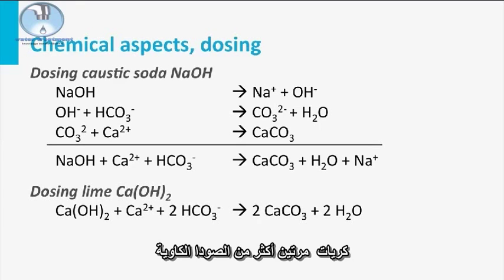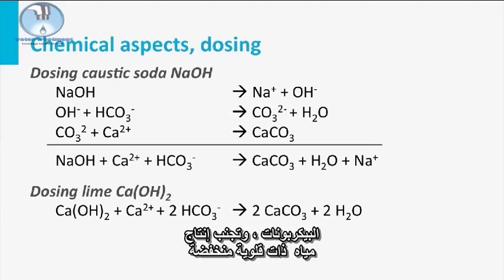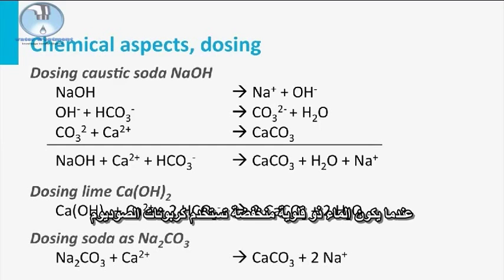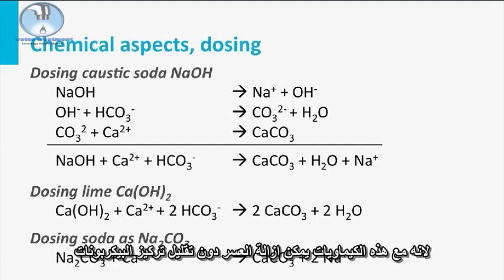Lime is therefore only used in case of waters with high calcium concentration and a high bicarbonate concentration, avoiding the production of low alkalinity waters. When water has a low alkalinity, soda ash is used, because with this chemical the water can be softened without a decrease in bicarbonate concentration.